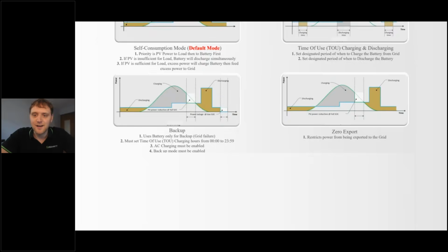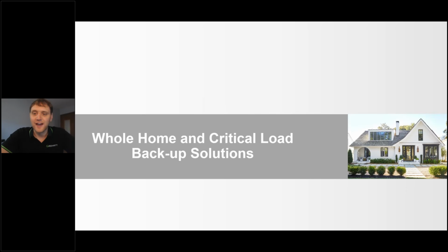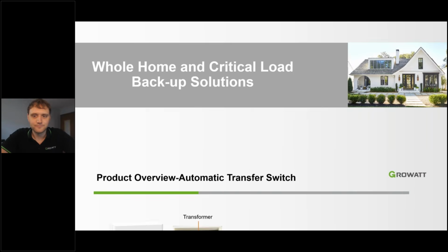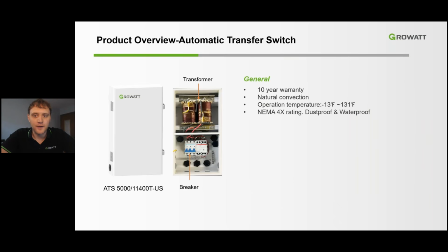So going into our next step, lastly, we have a look at the backup solutions that Growatt offers to support you and your customers' independence from the utility and create resilience in the home's electrical system. So this is for the V2 model of the inverter. Remember, there are two essential models of the inverter. There's the V2 and the V3, and here it becomes important. The automatic transfer switch is for the V2 model of this inverter. Growatt produces the automatic transfer switch to allow for critical load backup.